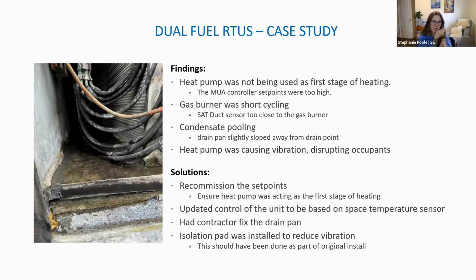Some of the older ones, you need to physically put a USB in and out, but the newer ones have apps. So you can monitor some of those points via an app without a building automation system. That way you can say, oh, hey, our compressor is cycling. Oh, wow, our heat pump isn't being used right now. It's only the gas. Okay, our set points are off. So it allows you to troubleshoot in a very similar way as you would with a building automation system, but without having to do a full building automation system upgrade. And then, of course, we fixed the contactor, the drain pan, isolation pad, did some of those basic things.